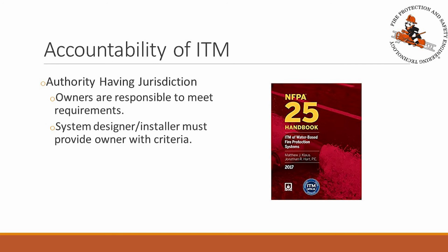Now, that doesn't mean that the owner themselves have to go out and test the sprinkler system. What it means is that they need to work with others that are specialized in those areas to provide that compliance with the authority having jurisdiction. Many times there are different contractors hired to help with the inspection, testing, and maintenance of systems. And those are important, again, because we're making sure that those systems are going to function when they are called upon, especially because many of these fire protection and life safety systems are stagnant unless you absolutely need them. For instance, water doesn't flow in a sprinkler system all the time unless there should be a fire.